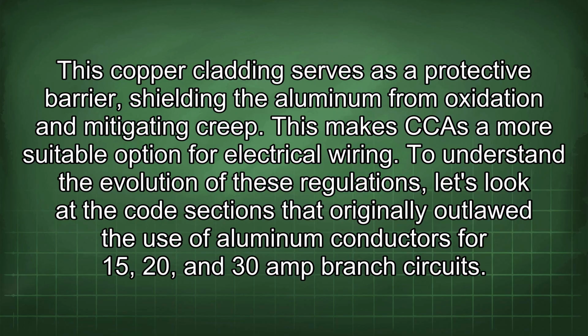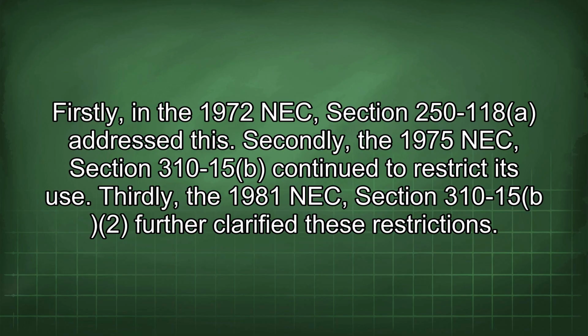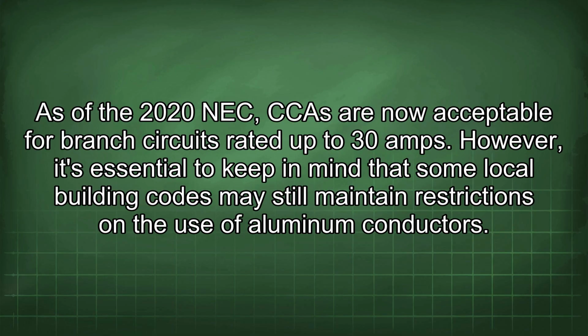This makes CCA a more suitable option for electrical wiring. To understand the evolution of these regulations, let's look at the code sections that originally outlawed the use of aluminum conductors for 15, 20, and 30 amp branch circuits. Firstly, in the 1972 NEC Section 250-118 address this. Secondly, the 1975 NEC Section 310-15 b continued to restrict its use. Thirdly, the 1981 NEC Section 310-15 b2 further clarified these restrictions. As of the 2020 NEC, CCA are now acceptable for branch circuits rated up to 30 amps.